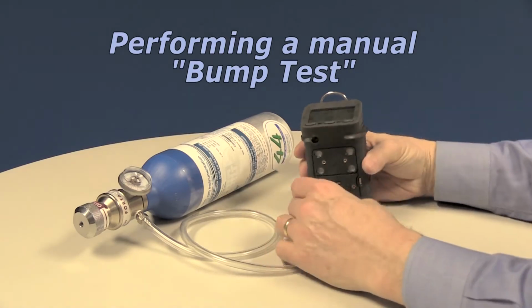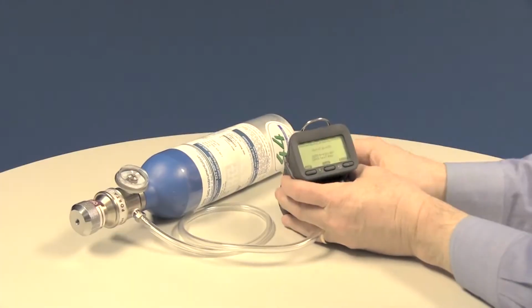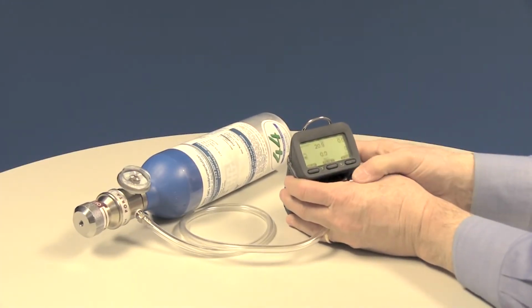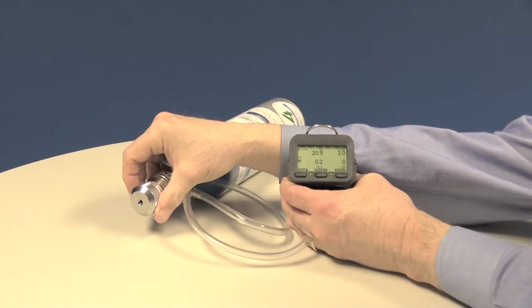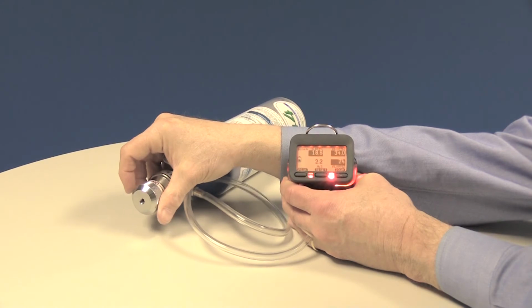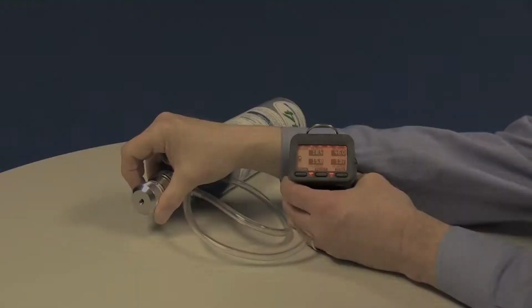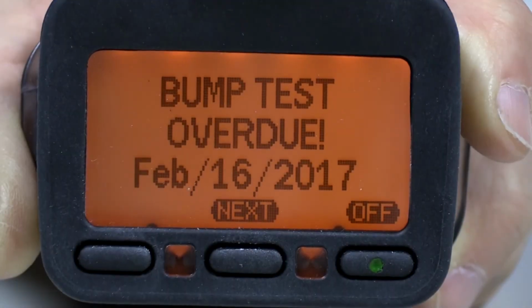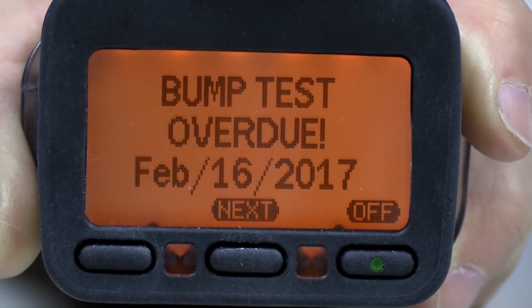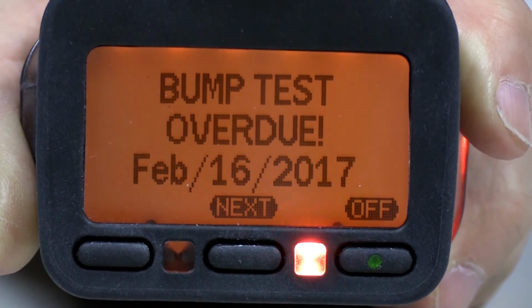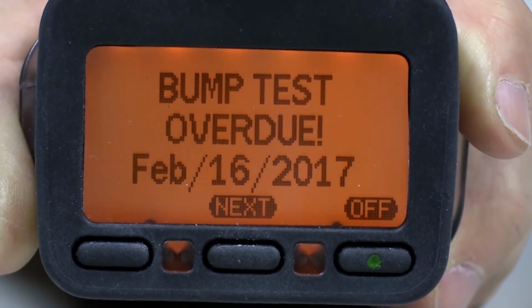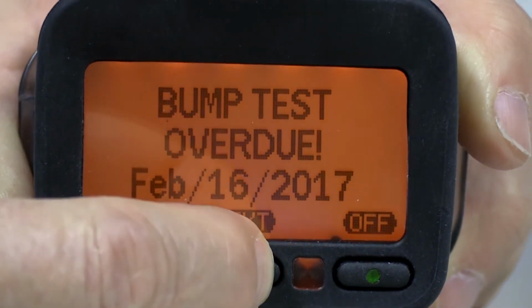Performing a manual bump test is easy. All you need to do is flow gas to the sensors, make sure that the alarms are activated, and verify that the sensors respond properly to the test gas. If the G450 displays a bump test overdue message during the startup sequence, the alarm can be acknowledged by pressing Next, but can only be cleared by means of using a DS400 docking station.